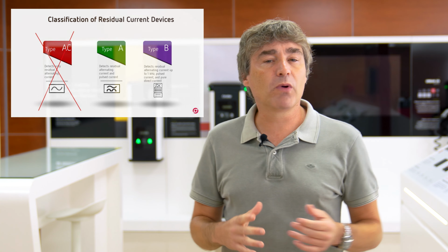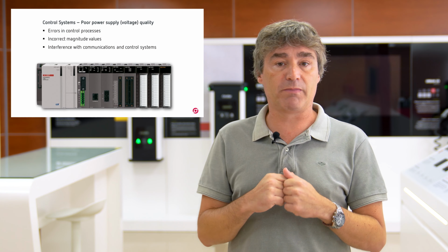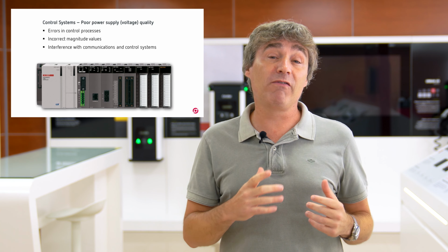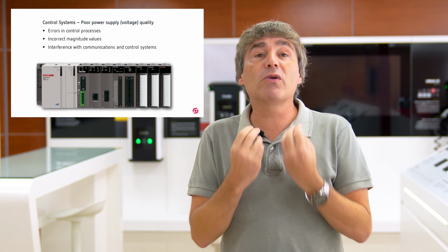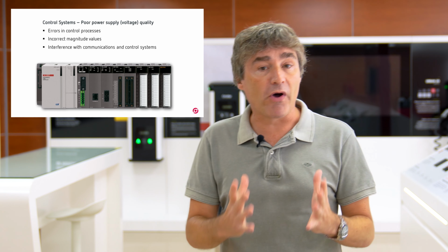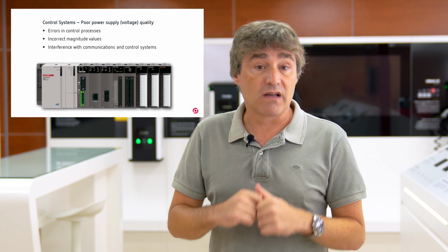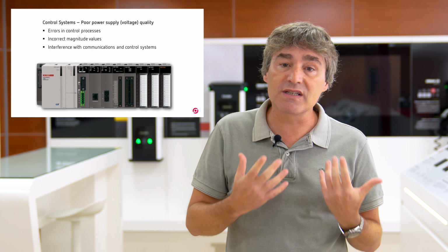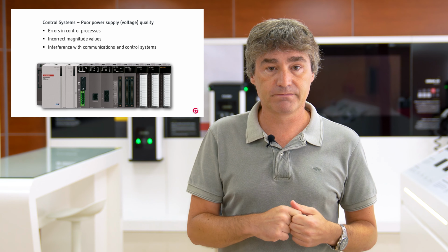We've been relating high voltage distortion rate with a poor voltage quality. Voltage THD rates over 5% can already be considered a high grade, and therefore it may lead to a malfunction of mainly sensitive electronic devices. Anyway, it is important to emphasize that although they are commonly blamed for it, voltage harmonics do not normally make electronic devices burn. When, for instance, a switch mode power supply is damaged, it is most likely due to an overvoltage event in the power grid.